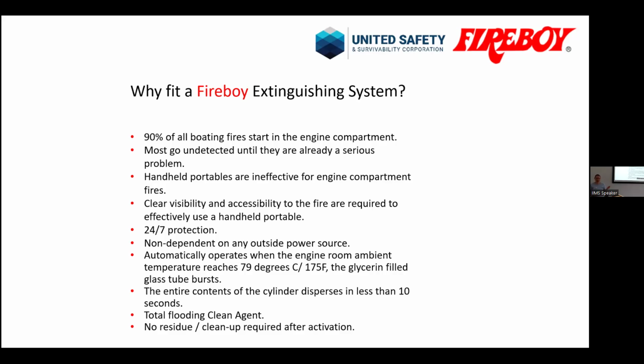Not so much on a manual because you have to have someone to operate, but we do manual, automatic combined, or manual only. So they're not dependent on any power source. Basically it's all mechanical activation. Automatic activation, the cylinder goes off automatically when the temperature reaches 79 degrees Celsius. So each head would have a glycerin bulb fitted that melts at 79 degrees and sets off the fire extinguisher. If you have the manual automatic version, if the fire is discovered prior to that, you would then activate manually by pulling a cord, or electronically. You can use a release panel and press the button.